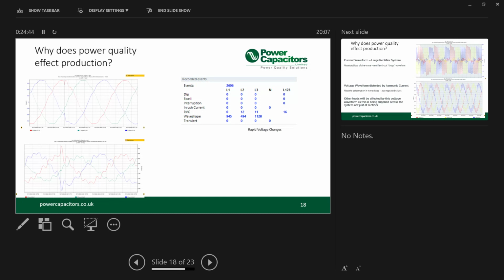Again, there's another little misfire. So it could be an inverter, but as far as the customer's aware, everything's working fine. There's no misfires, there's nothing going on, but we're showing that his efficiency is down. His efficiency is probably down about 2% on his whole supply there. Fixing that, we can improve that straight away.